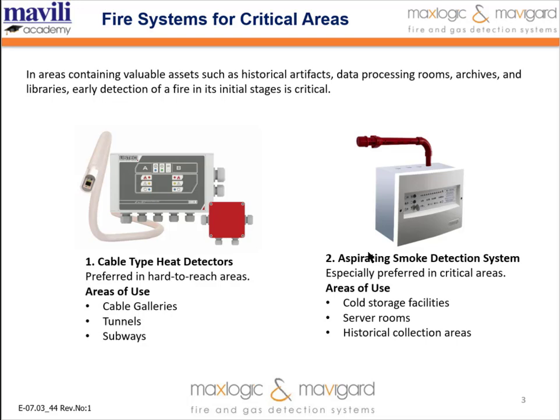First of all, in areas containing valuable assets such as historical artifacts, data processing rooms, archives, libraries, in these types of areas, early detection of a fire in its initial stages is critical, as you know. So the selection of fire detection systems in critical areas should not be based on a standard approach, but rather on the risk profile of the area.